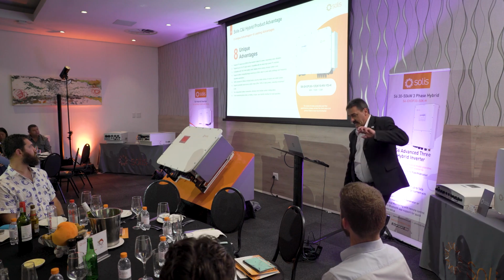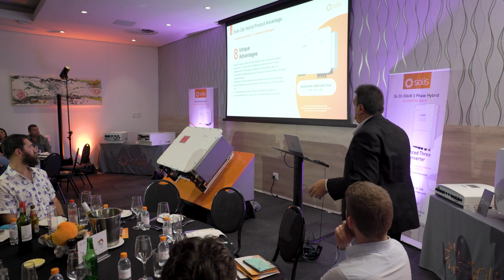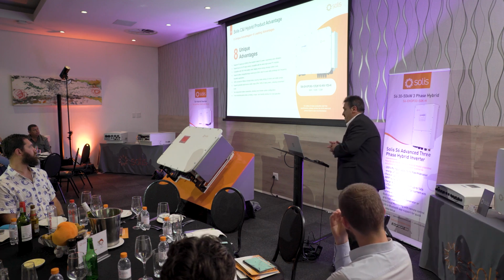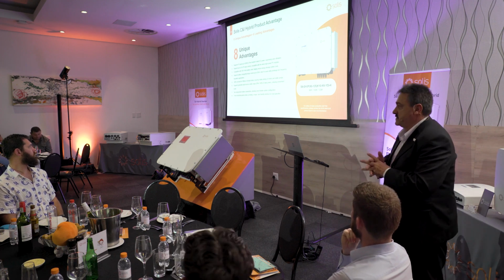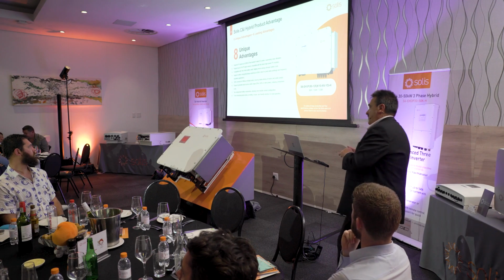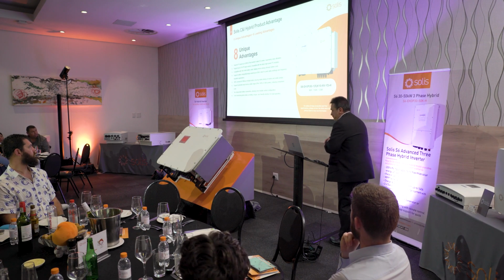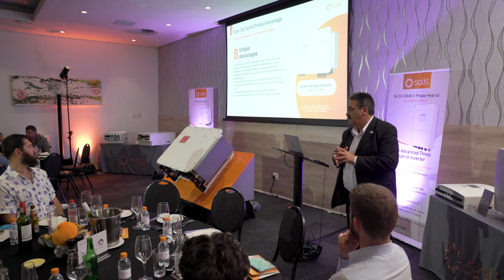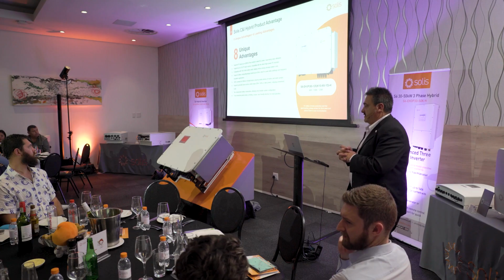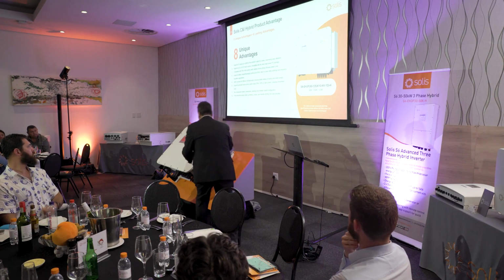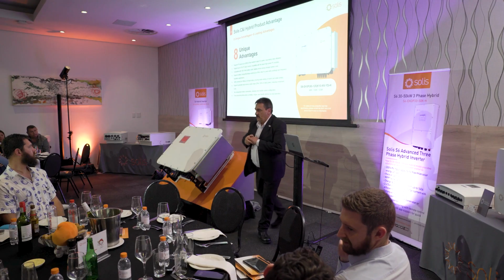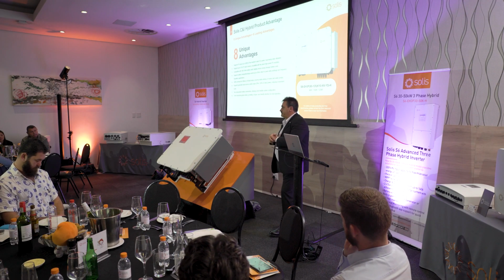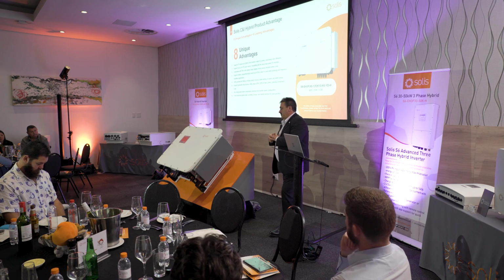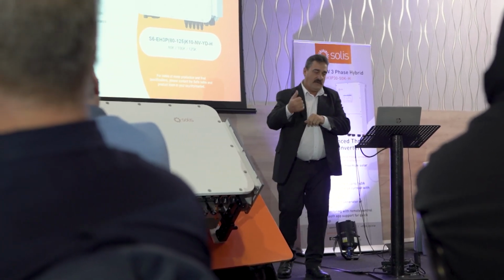Okay, so if we look at some of the unique advantages of the product, we spoke about a lot of stuff now. So this particular inverter will support 200% AC to DC ratio. Okay, it basically means that a 125 kilowatt inverter can be populated with up to 250 kilowatts worth of PV power. So it basically means that if you're running 100 kilowatt on your backup port here, for instance, you can still be taking 100 kilowatt to your battery at the same time. Or you could be charging the battery, let's say your backup ports are really low. At that point in time, you could be charging your battery and sending 100 kilowatts back to the grid if you are selling back to the grid.